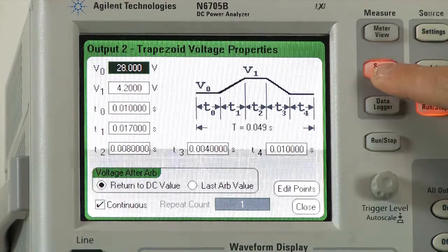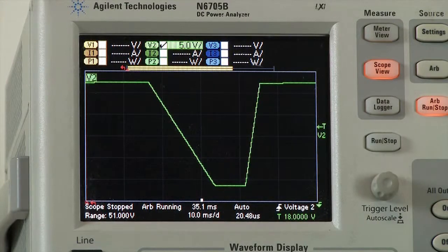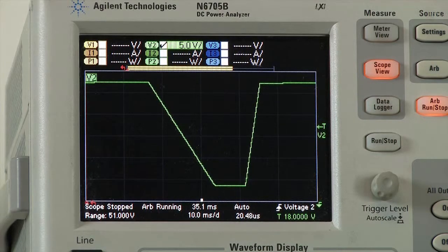I'm now going to the scope view and we can see the DC Power Analyzer's output digitizer captured the power supply transient — the interrupt that I had just generated.